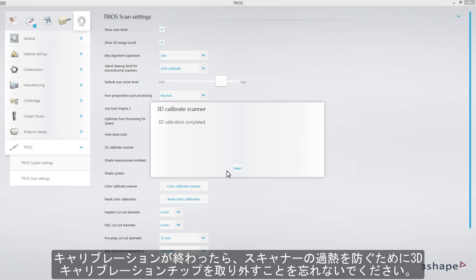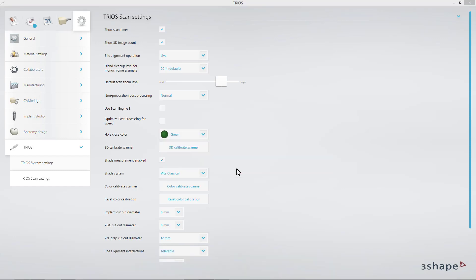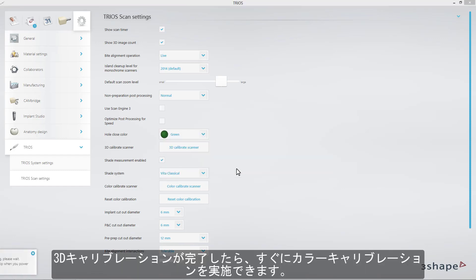When it is finished, remember to remove the 3D calibration tip from the scanner in order to prevent it from overheating. As soon as 3D calibration is completed, you can proceed with color calibration.